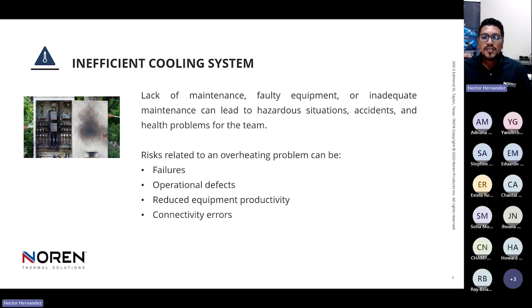Another problem is inefficient cooling systems. Another technology used to cool down electrical panels is air conditioning. However, this system has some issues because air conditioners have not been designed specifically to cool down electrical panels, since electrical panels sometimes operate in industry with dust or even high humidity levels in the ambient. The filters of the air conditioning system get clogged, so we can reduce the performance of the air conditioning system, or even the air conditioning can shut down.